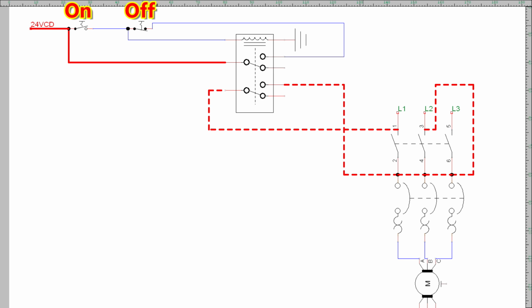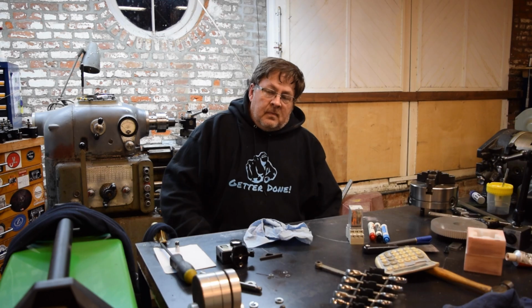When you press the normally open on switch, a couple of things happen all at once. Voltage is applied to your normally closed off switch, and the coil on the octal relay is energized. This does two things. One thing that happens is that control voltage is passed through one set of relay points and travels back around to your normally closed off switch. The other thing that happens is the contactor closes and high voltage is applied to the motor, energizing the motor. Congratulations, your lathe is now running. This is your normal state of being until you press that normally closed off switch, at which time you'll de-energize the coil in the octal relay and everything will go back to its state at rest. All right, there you go.